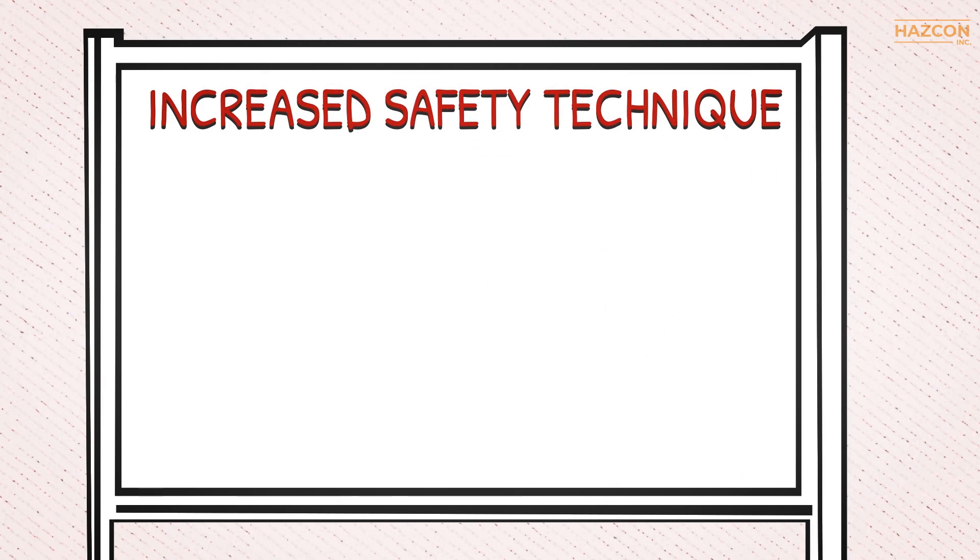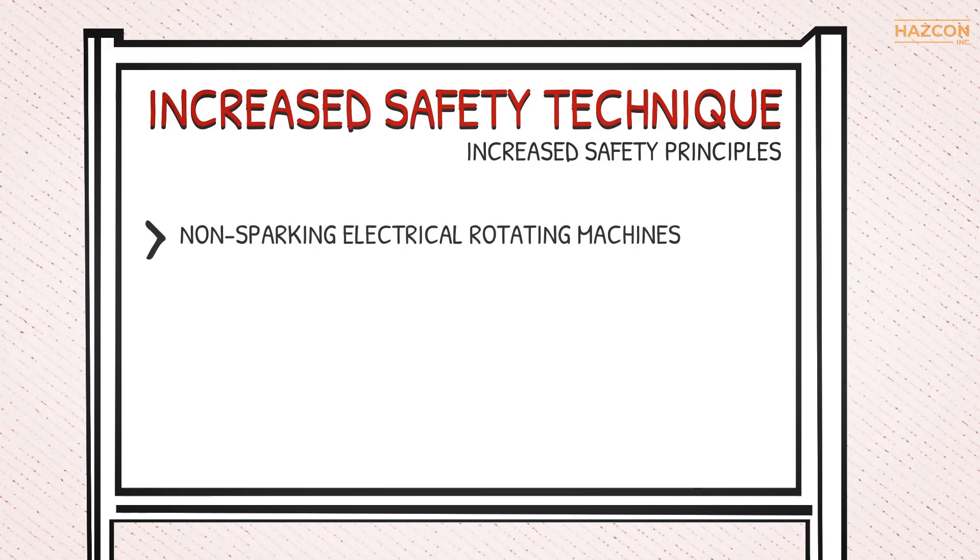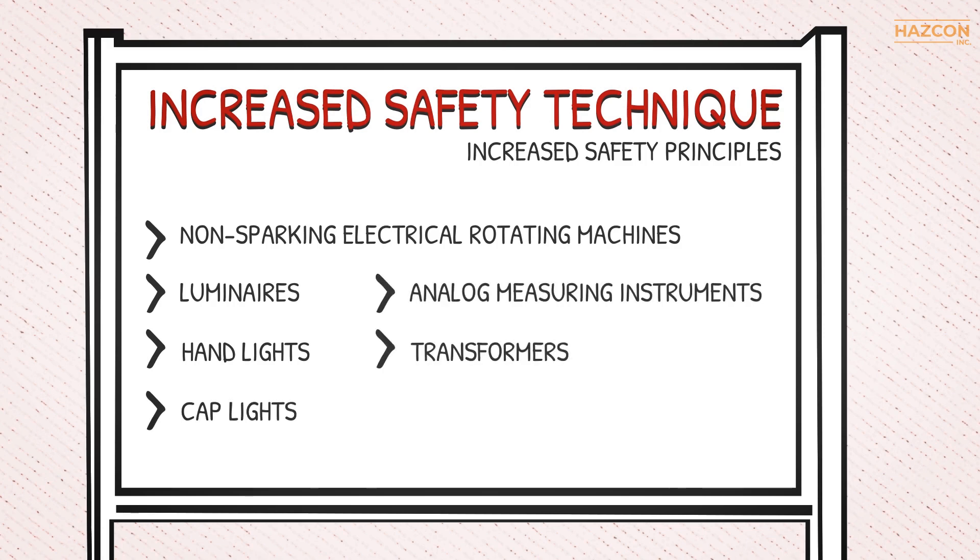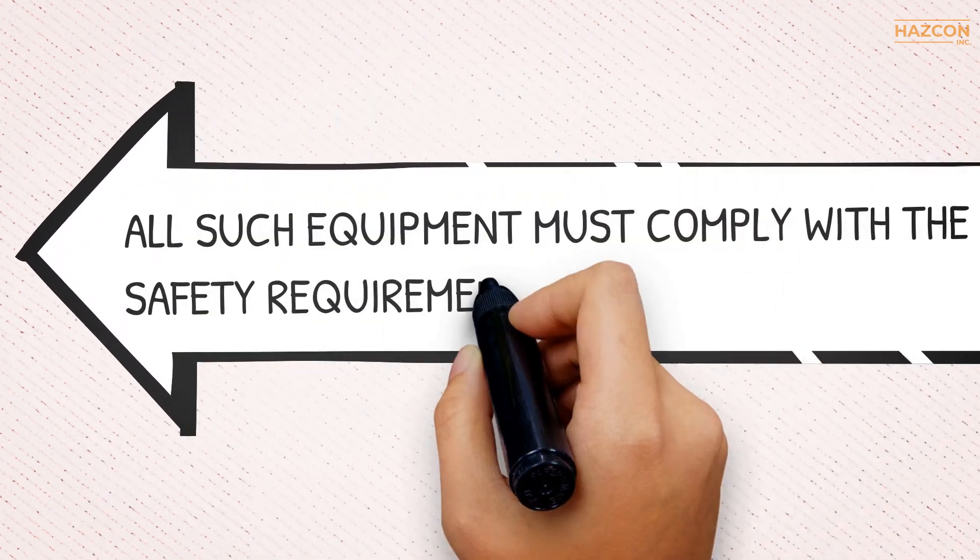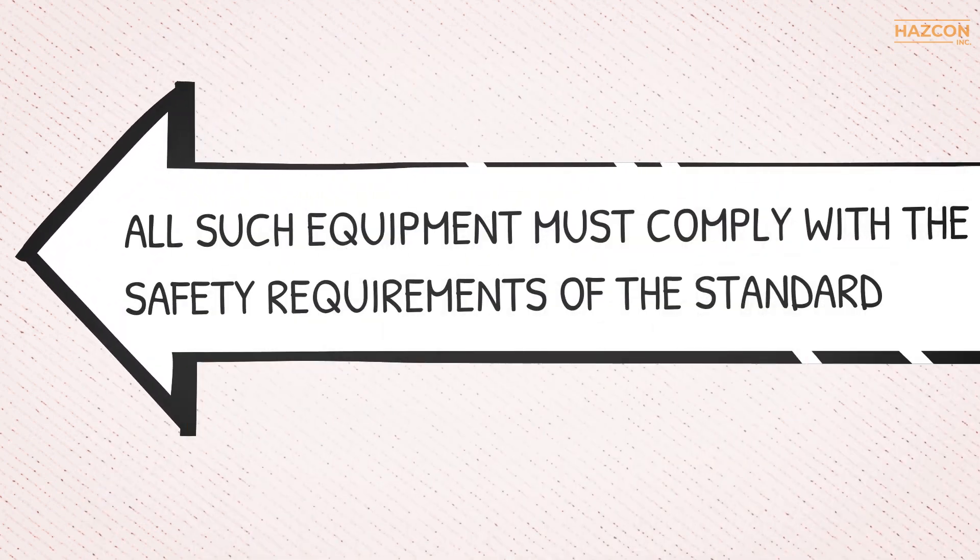Certain products may also use the increased safety technique if they comply with the standards and are designed based on increased safety principles. Examples of such devices are non-sparking electrical rotating machines, luminaires, hand lights, cap lights, analog measuring instruments, transformers, and resistance heating equipment. All such equipment must comply with the safety requirements of the standard.